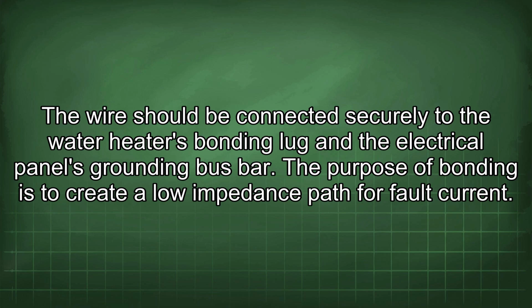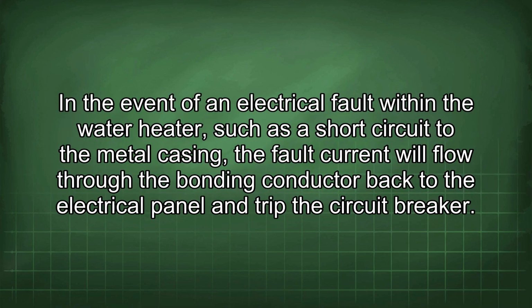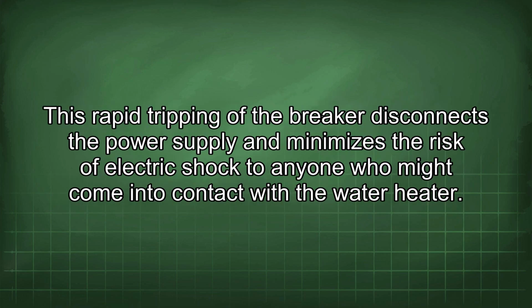The purpose of bonding is to create a low impedance path for fault current. In the event of an electrical fault within the water heater, such as a short circuit to the metal casing, the fault current will flow through the bonding conductor back to the electrical panel and trip the circuit breaker. This rapid tripping of the breaker disconnects the power supply and minimizes the risk of electric shock to anyone who might come into contact with the water heater.